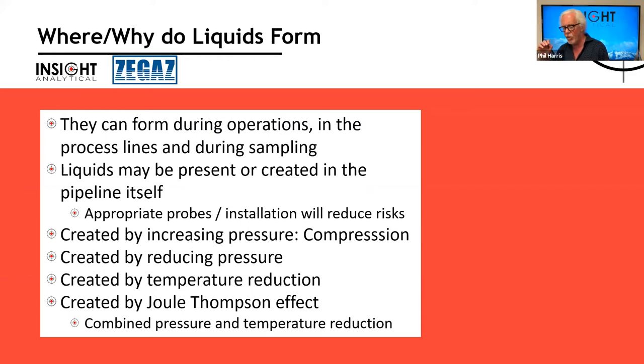But even then, liquids can drop out when we change the pressure. So during compression, liquids can start to drop out. When we go back and look at that phase diagram, we're going to show why these things happen. They can be created because we've reduced the temperature. And even when we put in things like a needle valve or a regulator, when we take a large pressure drop, we get a thing called the Joule-Thompson effect, or adiabatic cooling. When you drop the pressure of a gas, it cools. And so you drop the pressure, and that leads to a temperature reduction, which can cause us to get condensation.